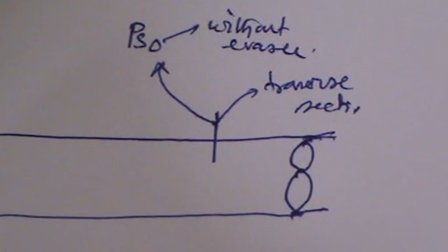Now without the diffuser we will measure the static pressure here, and also we measure with the anemometer the velocity at the inlet, and if you multiply this by the area of cross section here, you will get the quantity flow to the system. Now after measuring this, we will attach the diffuser to the system.